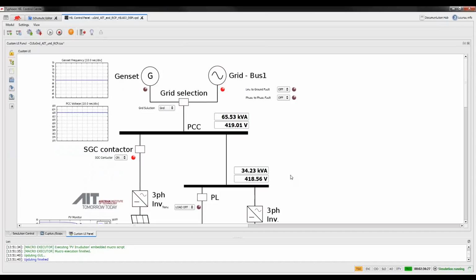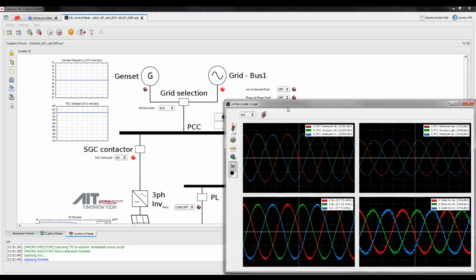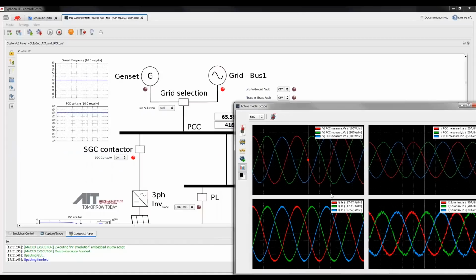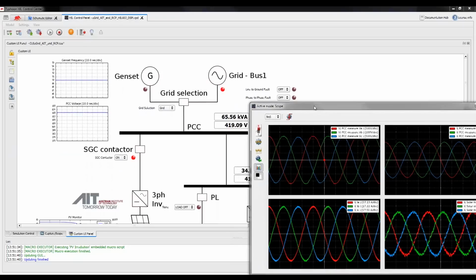You can interact with our simulation. So you can basically see now we are in steady state. Let's look at the waveforms here as well. We are in steady state, point of common coupling here. We can see that the grid selection, we have selected the grid active. So the genset is actually now not engaged. So we are connected directly to the grid.